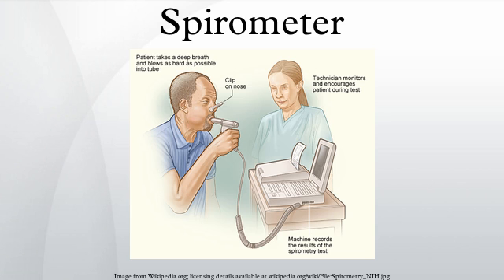Fully Electronic Spirometers have been developed that compute air flow rates in a channel without the need for fine meshes or moving parts. They operate by measuring the speed of airflow using techniques such as ultrasonic transducers, or by measuring pressure differences in the channel. These spirometers have greater accuracy by eliminating momentum and resistance errors associated with moving parts such as windmills or flow valves. They also allow improved hygiene between patients by permitting fully disposable airflow channels.